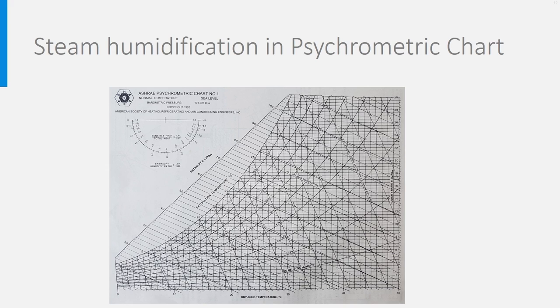If we look at the process in the psychrometric chart, we plot here again point 1 and then the line of constant absolute humidity at 6.8 grams. Then we need to go first to the protractor above and draw here from the point in the middle the line of dh over dx is 2675, expressed in the protractor as 2.7, so divided by 1000. We draw then a line parallel to this one, but starting from point 1. At the intersection, we'll find the final point 2.